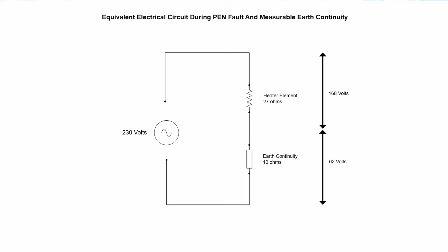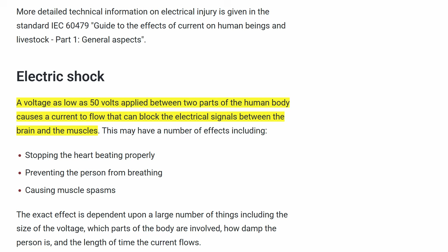If that earth resistance is just 10 ohms, which it could easily be if not more, then the voltage on the metal case of our heater is 10/37ths of 230 volts, which would be just over 60 volts - more than the 50 volts AC considered potentially dangerous. For context, an earth rod, something designed to provide a reasonably low resistance earth path, is expected to provide an earth with a resistance of about 20 ohms, twice what we said our pipes might provide.